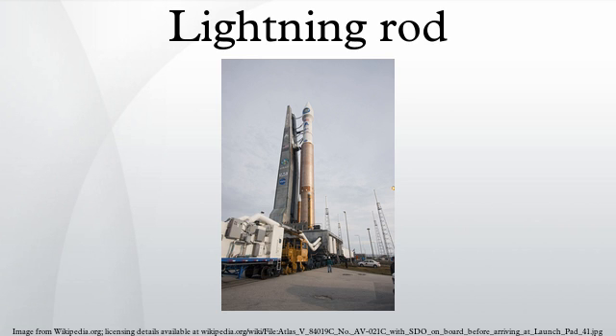Lightning protection systems are used to prevent or lessen lightning strike damage to structures. They mitigate the fire hazard which lightning strikes pose to structures. A lightning protection system provides a low impedance path for the lightning current to lessen the heating effect of current flowing through flammable structural materials. If lightning travels through porous and water-saturated materials, these materials may literally explode if their water content is flashed to steam by heat produced from the high current. This is why trees are often shattered by lightning strikes.